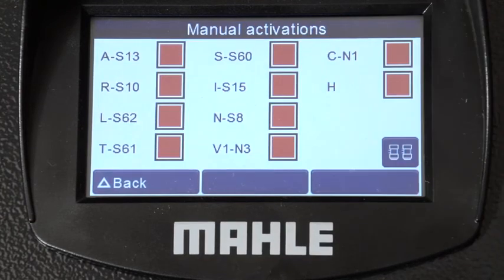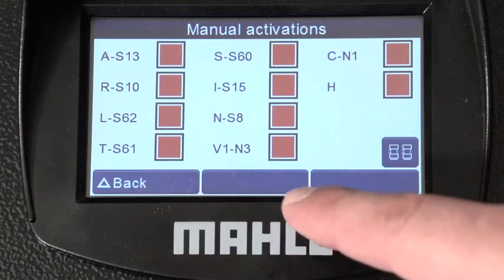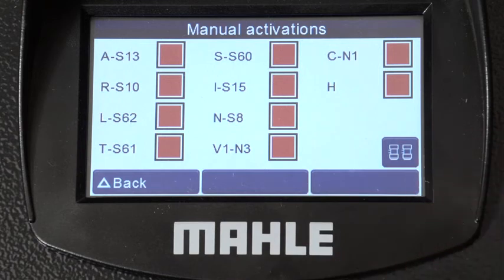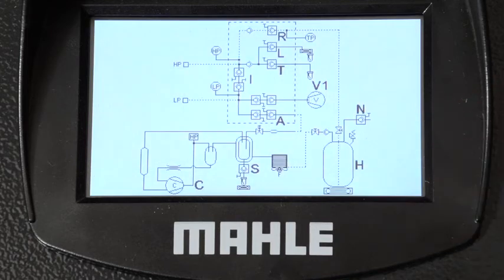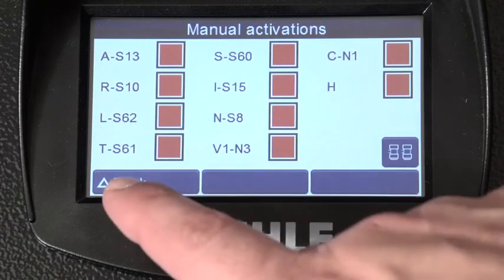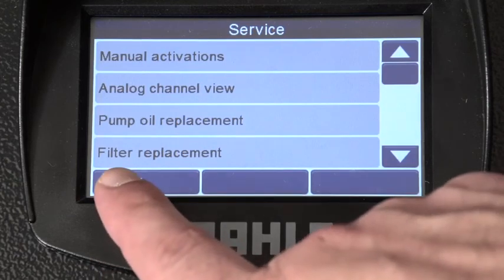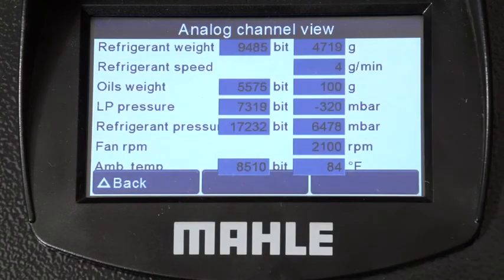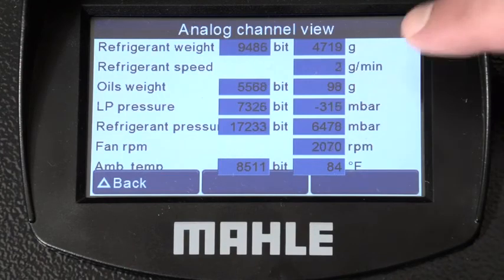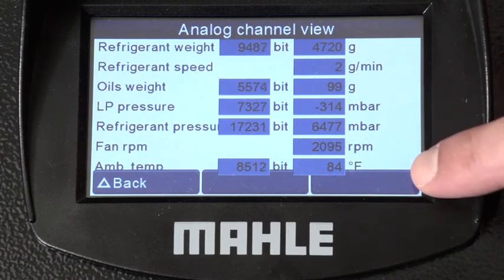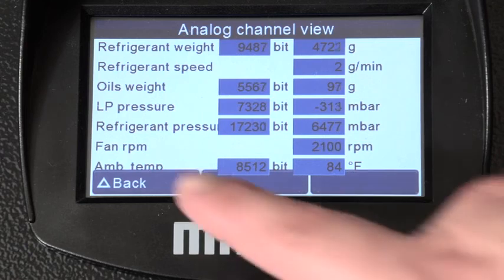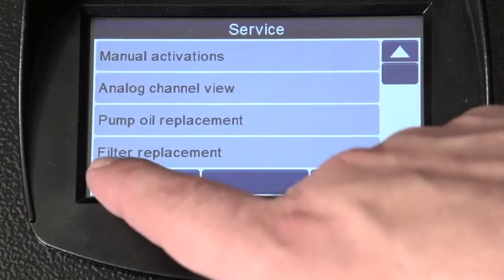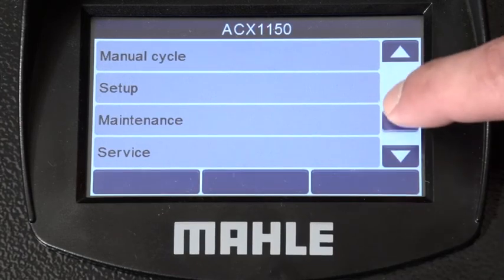Manual activations is our input-output diagnostics. And we have the solenoids and the pumps that we can manually activate on and off. We hit this button and it gives us a picture of the machine schematic with the labels. Touch the screen again and it'll take us back to the manual activation screen. Analog channel view. This is our information here. It gives us all of our weights, our pressures internally, temperature. Go back, takes us back to our main menu.